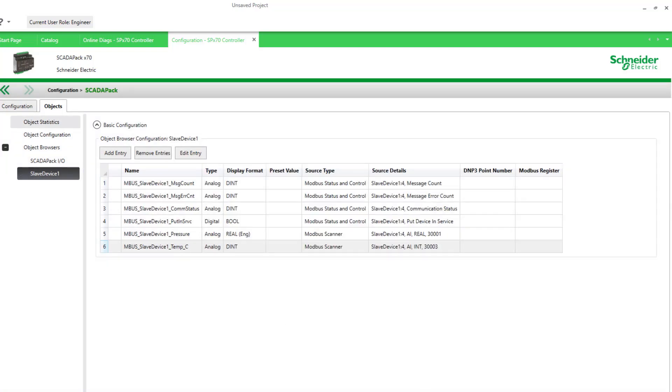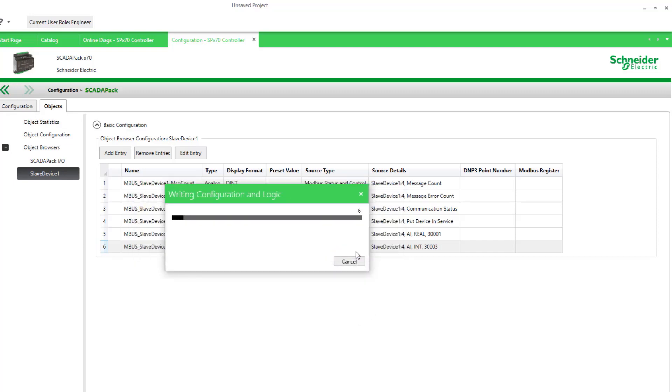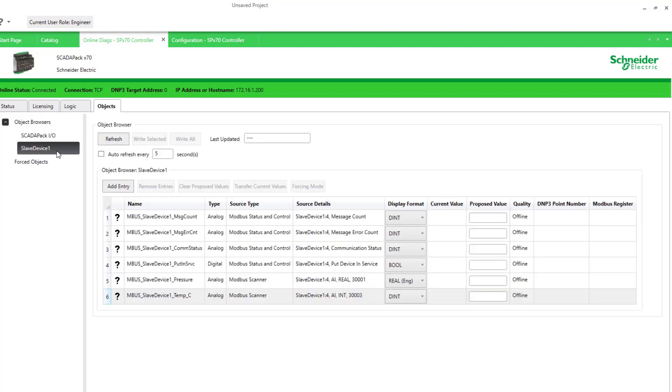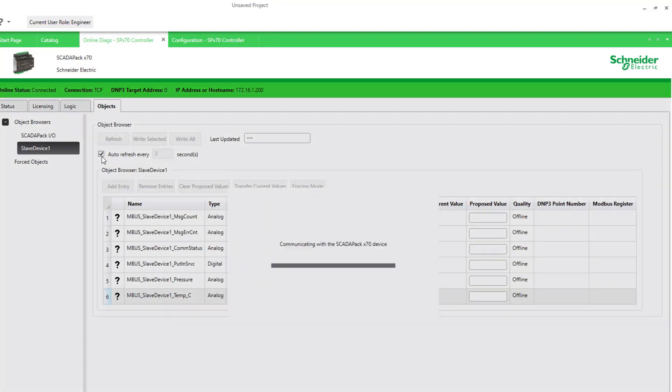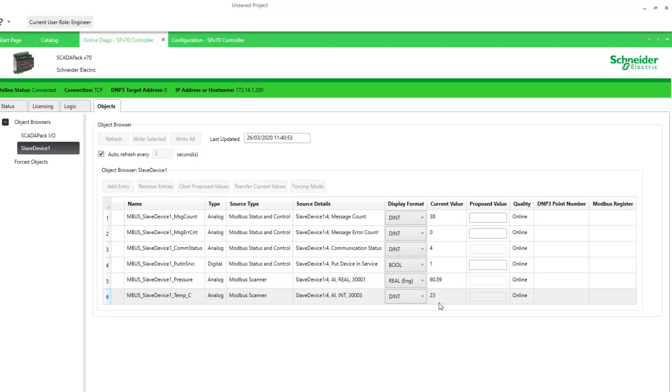Apply. Now, we've renamed the object, so I will write that to the controller. Back online in our object browser, refreshing twice every two seconds. Now we have the labels of pressure and temperature. And here's our real display. So 60 psi or whatever the units are. If I change the value at the source, we'll see the value change. I've lowered the temperature and increased the pressure.